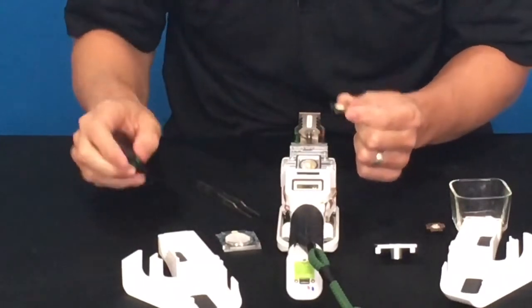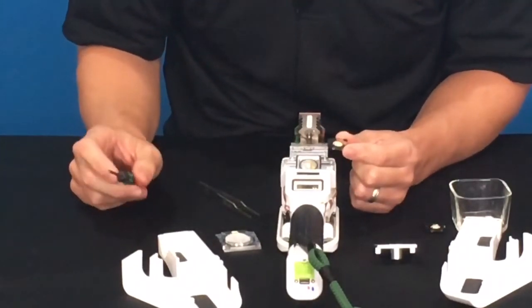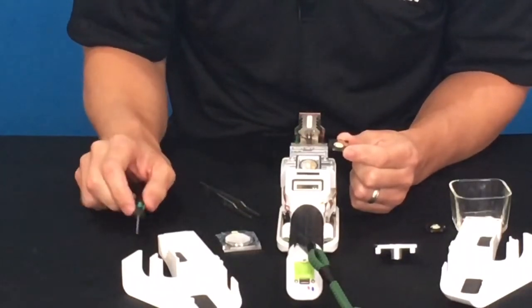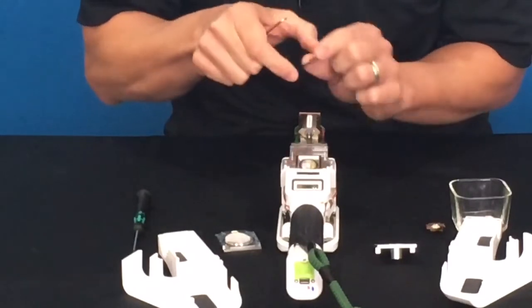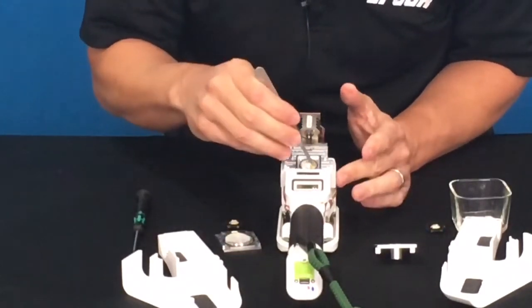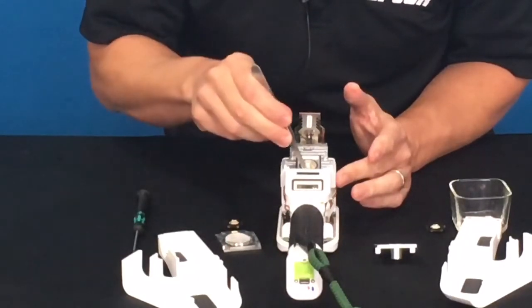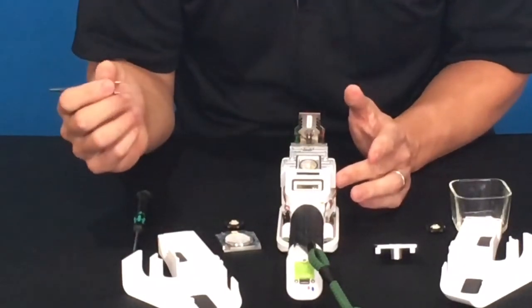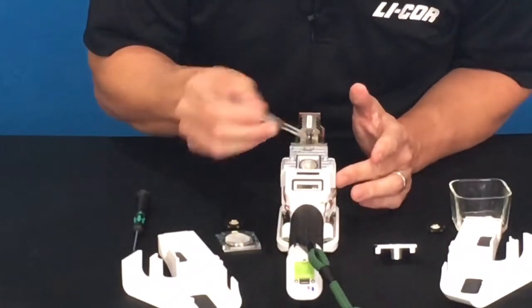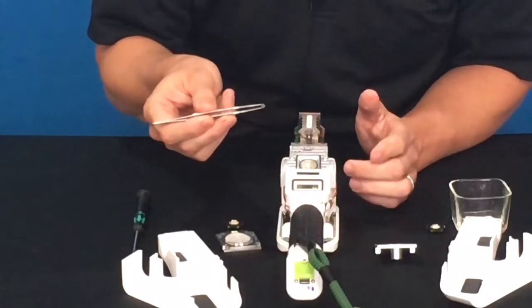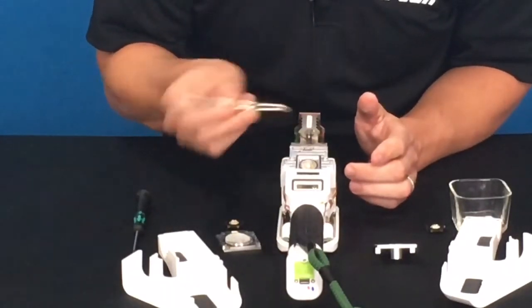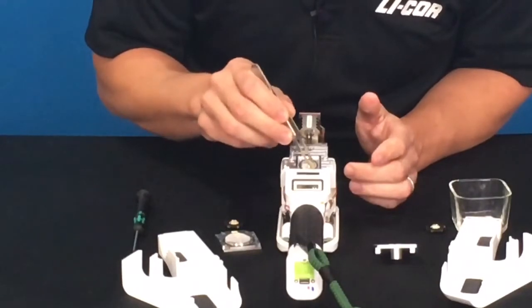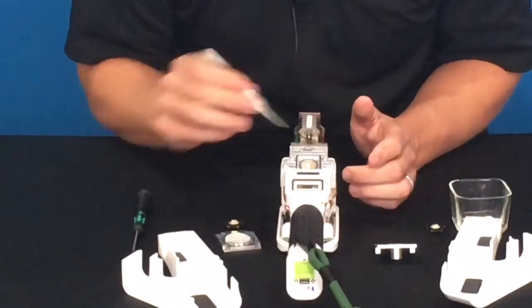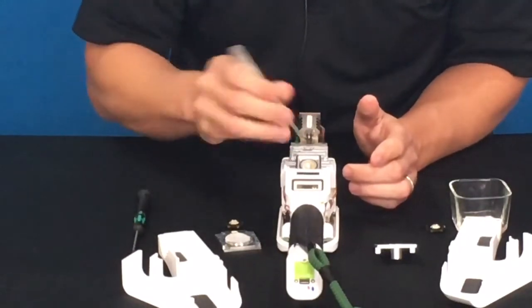One other reason to access this area is to check the zero of your RH sensors if you're going to be using the scrub tube provided in the instrument. Our water buffering material is located right here—these small beads underneath the pump. If you try to zero your RH sensors with these beads in place, it will take a very long time to reach zero, if ever. These really do a great job of buffering water, and it's not recommended to check your zero with these beads in place. So you would need to remove those beads and store them somewhere separately.